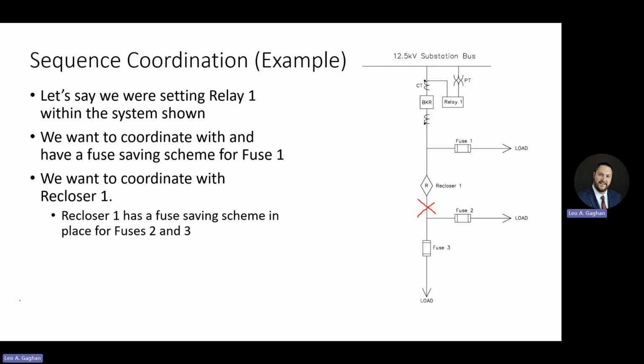When we can pull that off, the customers off of fuse 1 aren't going to lose power. Recloser 1 can isolate the fault like it's intended, and the breaker being tripped by relay 1 can stay closed, and everyone's happy. So that's the basic principle. I don't have any example relay logic for it to show you guys right now. It is quite involved, more so than the cold load pickup logic. So I left that out.